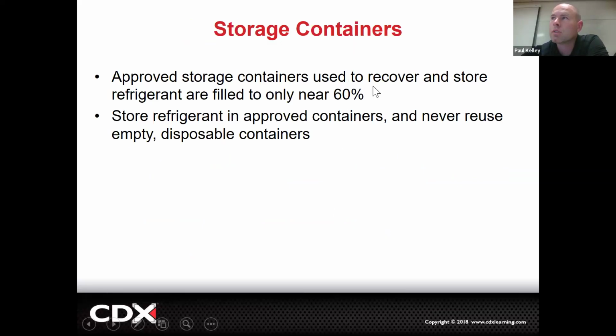We do have approved storage containers—we can recover and store refrigerant in those, but they're only filled around 60%. We can't completely fill them because we need a little room for the liquid refrigerant to be at the bottom and the gaseous refrigerant at the top. That gas refrigerant gives us a buffer for expansion if it gets slightly warmer, so mainly it's to make sure it stays a vapor—it's also for safety.